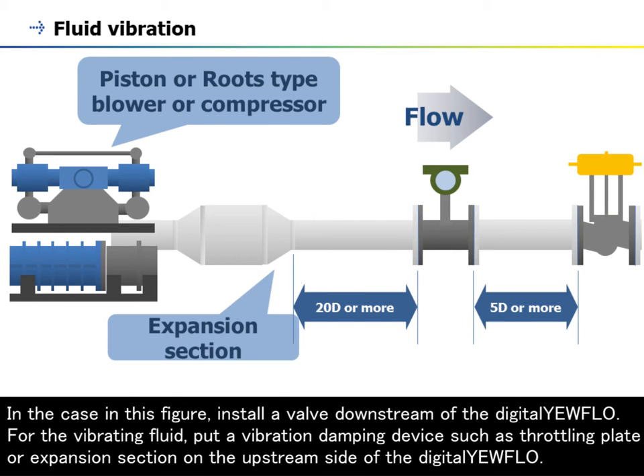In the case shown in this figure, install a valve downstream of the digitalYEWFLO. For the vibrating fluid, put a vibration damping device such as a throttling plate or expansion section on the upstream side of the digitalYEWFLO.